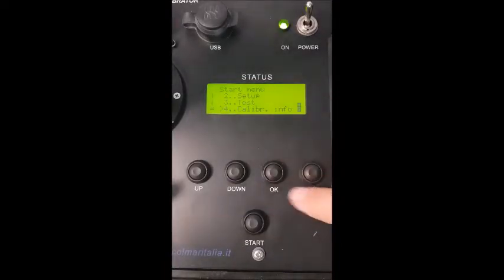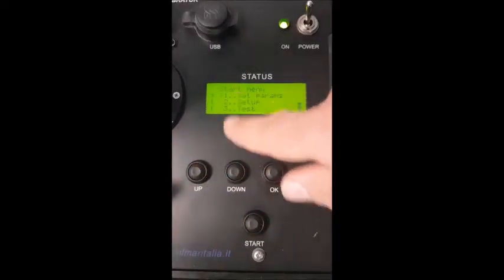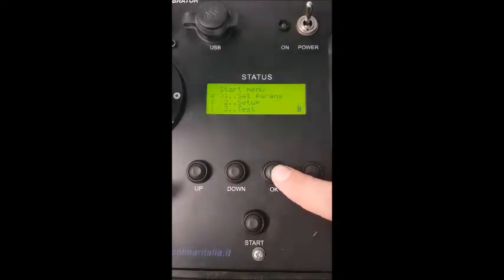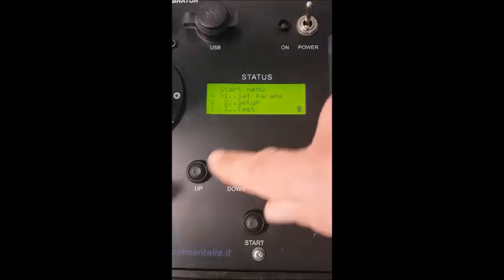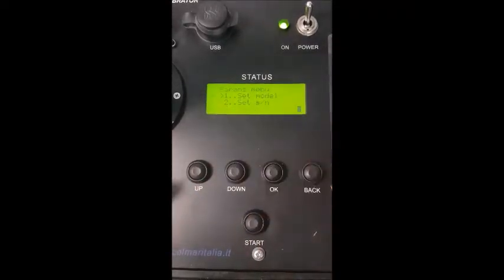Let's start from the first menu. We can move and select each submenu by using the up, down, and OK buttons. So the first submenu is set parameters. Once you enter the menu, you can set up the model and the serial number of the hydrophone being calibrated. This is done purely so that the model and serial number appear in the comma-separated values file downloaded from the USB port, so that if you do more than a single calibration, you can then know the model and the serial number of the hydrophone the data refers to.